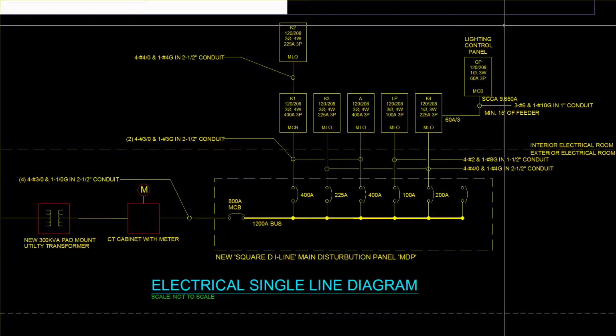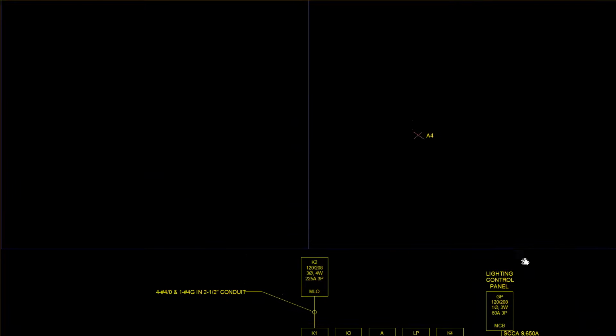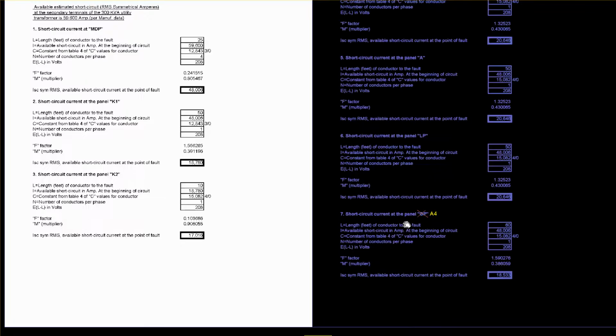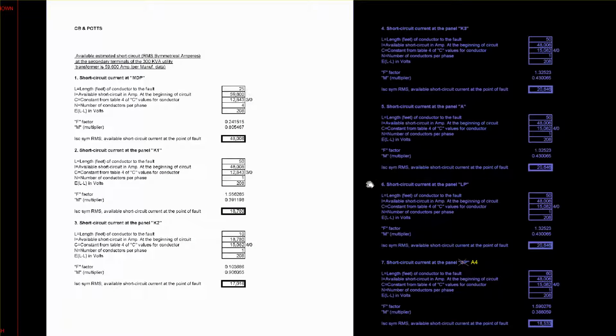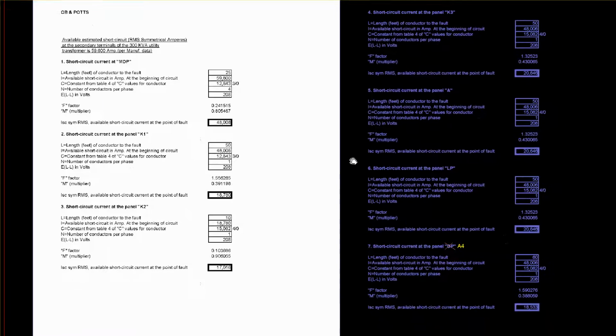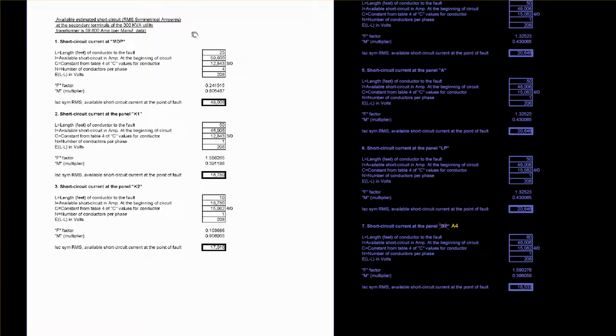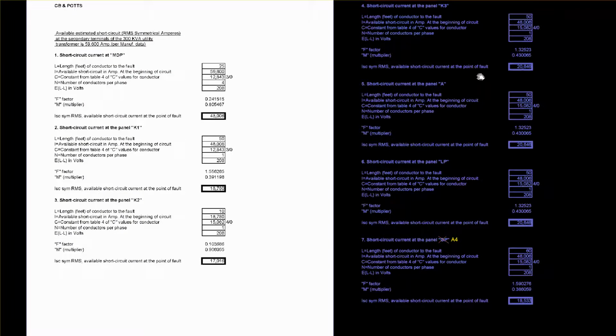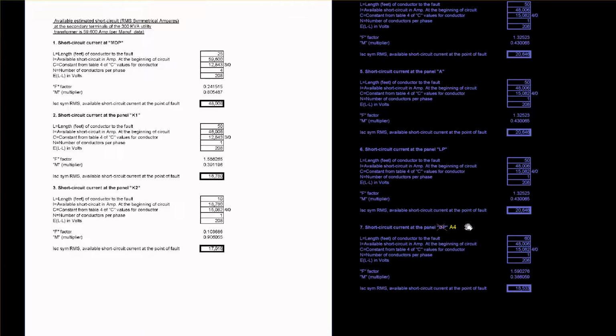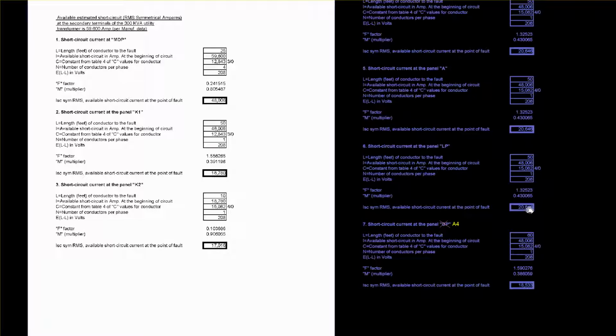Also, in this particular drawing, let me show you a fault current study that has been accomplished by this particular designer, and you'll see the different sets of energy. So you have different short circuit currents at the MDP, at K1, at K2, at K3, at panel A, LP, and then A4. And you'll see in these boxes the different short circuit current or fault current ratings. Or fault current available, I'm sorry. And so these different fault currents available, that's important information. And the engineer can look at this.